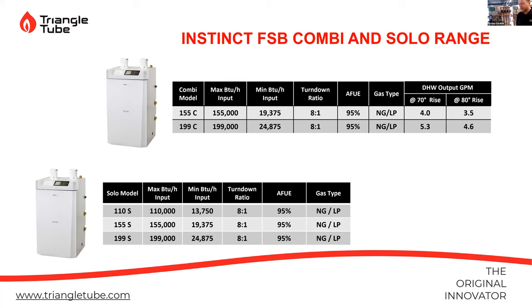So with the combi boilers, pretty much the same models. We have a 155 combi, 199 combi. 4 gallons a minute on the 155, 199 gets about 5.3. Solo models, pretty much the same, 110, 155, 199. But again, we have the system pump, the boiler primary pump installed, and your primary piping's already done. So on these floor boilers, you're just gonna come off the low loss header on the supply side, go right off to your zones, because that low loss header is your air separation, your hydraulic separation, your dirt separation, all in one unit. So you just come off, go to your zone tees for the supplies, and then on the returns, you just bring it right back with your return tees and your boiler fill.